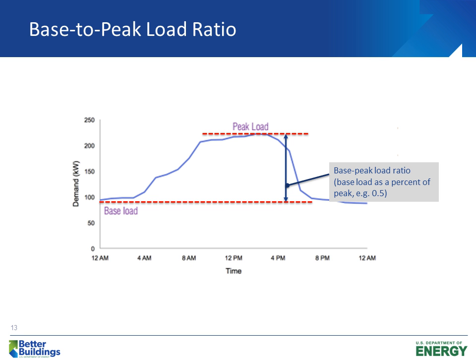Another metric is base to peak load ratio. A lot of people are working on reducing their base load, and a metric to look at this is called base load to peak ratio—basically dividing your average base load by your peak. In this example it's 0.5; we like to see it more like 0.3. It depends on your building type, whether you have data centers or labs running 24/7, and so on. You can benchmark your base load against yourself over time and try to reduce it, or for office buildings, 0.3 or less is pretty good, while 0.5 has room for improvement. An EIS can automatically calculate these metrics for you, so you don't have to manipulate any data to get this baseload to peak metric.